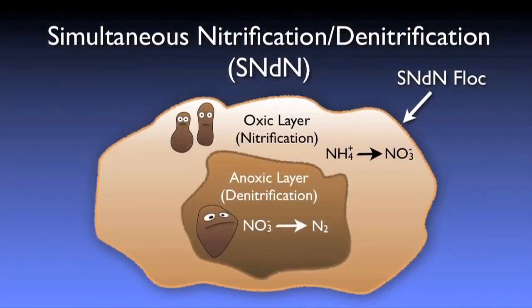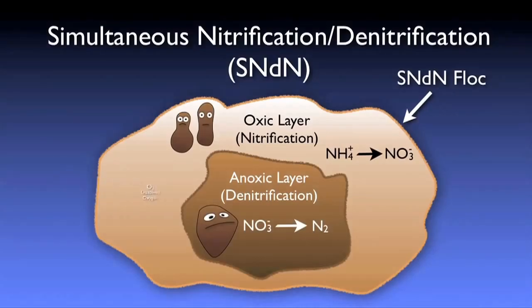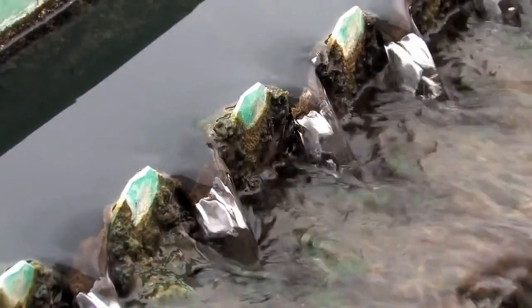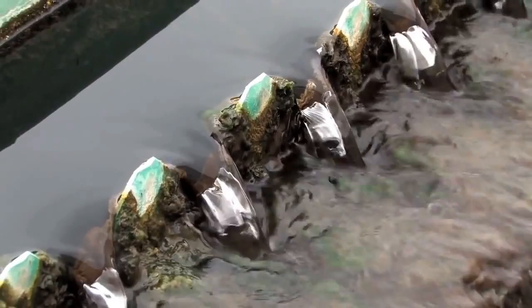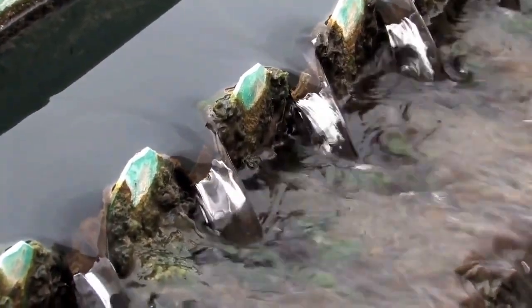Under certain conditions, micro-anoxic zones can be developed within the bacterial flocs themselves, resulting in what is referred to as simultaneous nitrification-denitrification. Various levels of denitrification may be required depending on the local discharge permit. However, full biological denitrification typically results in only 1–3 mg/L of nitrate in the effluent stream.